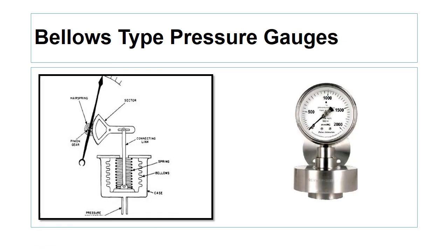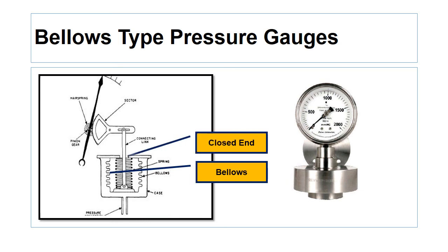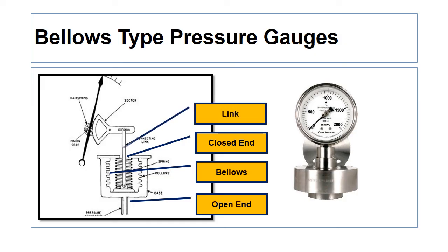Bellows are thin-walled metallic cylinders with deep convolutions. One end of the bellows is closed and the other end remains open. The closed end can move up freely, while the open end is fixed and open to apply pressure. When pressure is applied to the open end, the bellows are expanded, the closed end moves upward, and the link rod between the closed end and the transmission mechanism goes up and rotates the pointer.